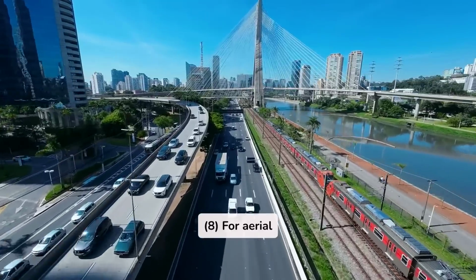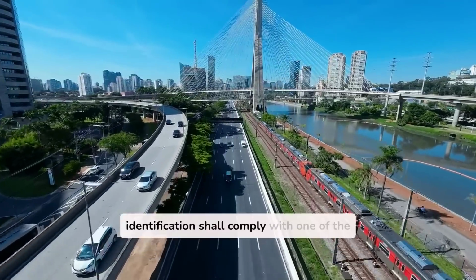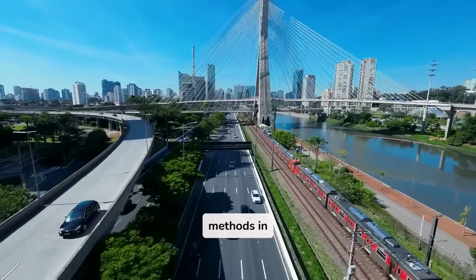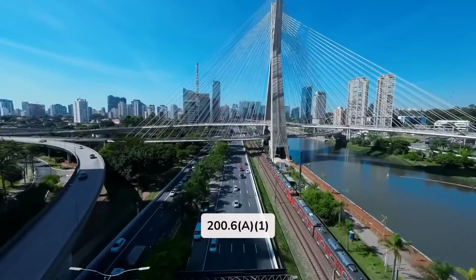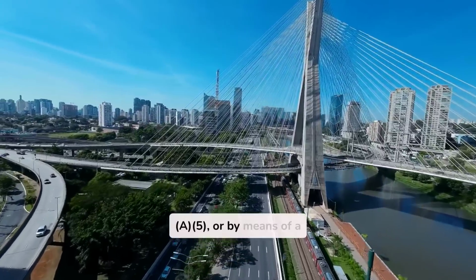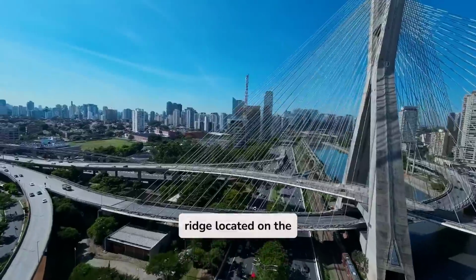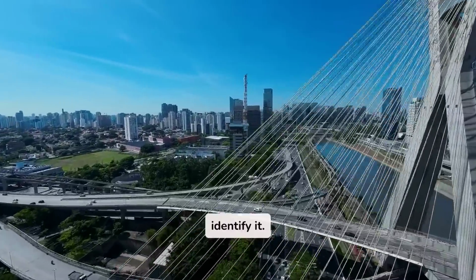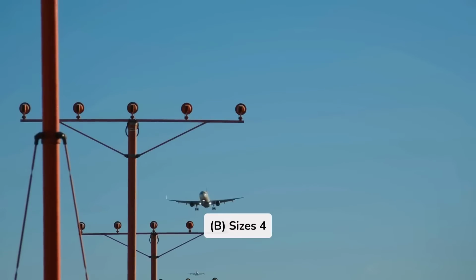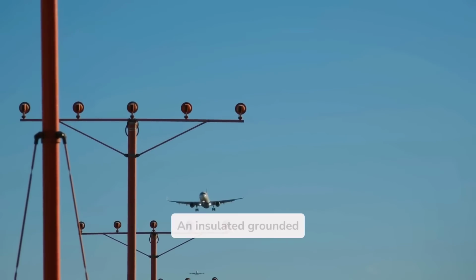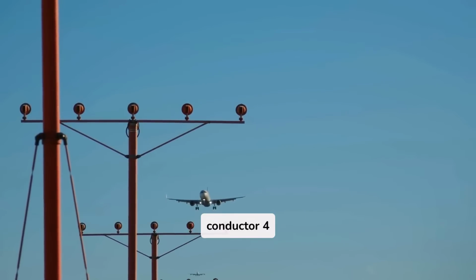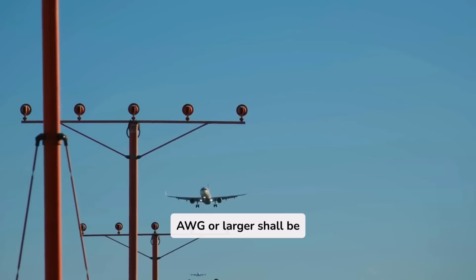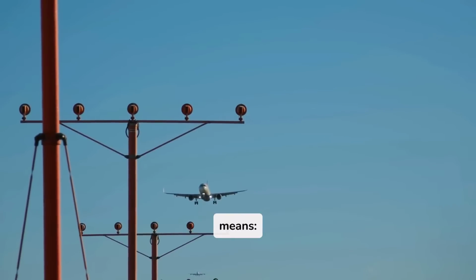8. For aerial cable, the identification shall comply with one of the methods in 200.6(A)(1) through (A)(5), or by means of a ridge located on the exterior of the cable so as to identify it. B. Sizes 4 AWG or larger. An insulated grounded conductor 4 AWG or larger shall be identified by one of the following means.